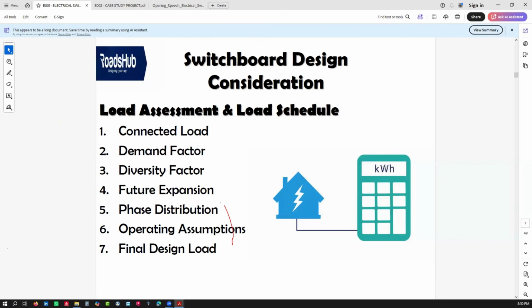That's why we do load assessments. You check all the connected loads. But remember, we have something called demand factor, and it brings us very close into these systems because we want a cost-effective system. So what is your demand load? We need to include diversity factors if you're designing a system from different machines or different types of loads. We have factors we include when we do design. I have a case study and we will see that.